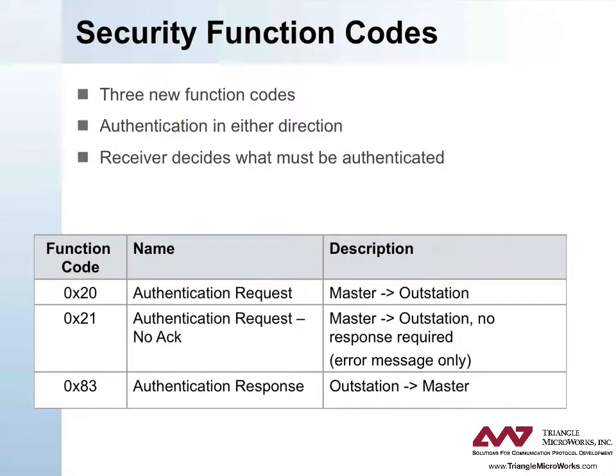In practice, the core of the DNP3 secure authentication mechanism is three new function codes. Almost every security message will use one of these function codes. This permits non-secure devices to clearly identify that secure devices are using a feature they do not support, and raise a configuration error.